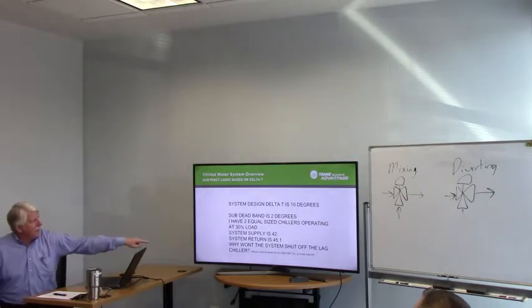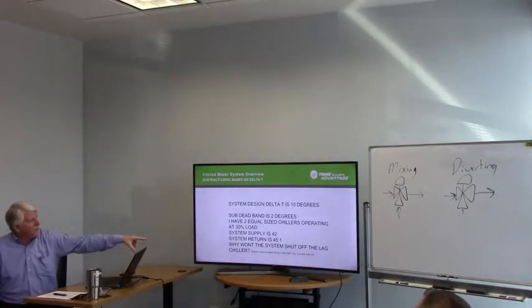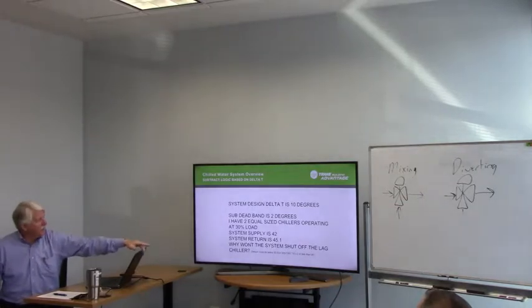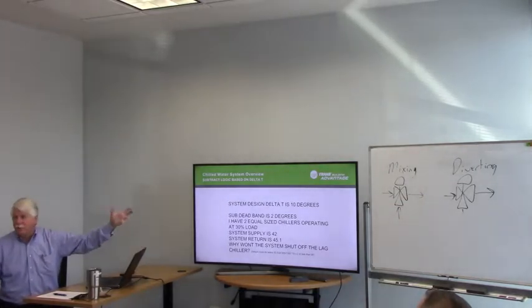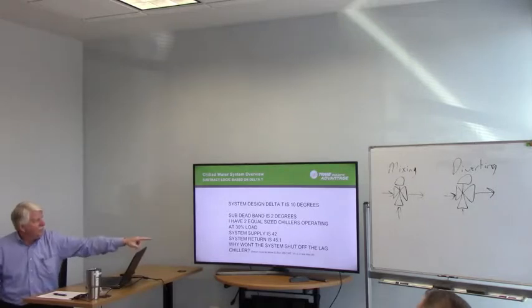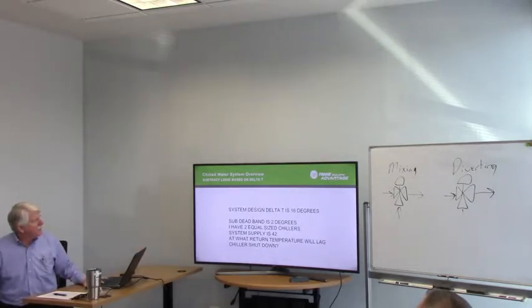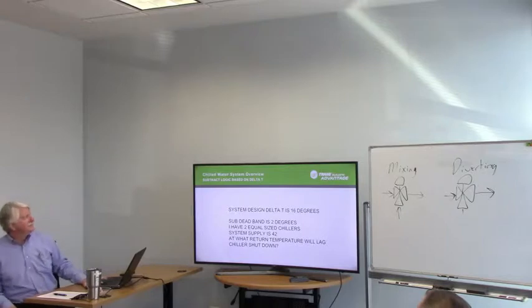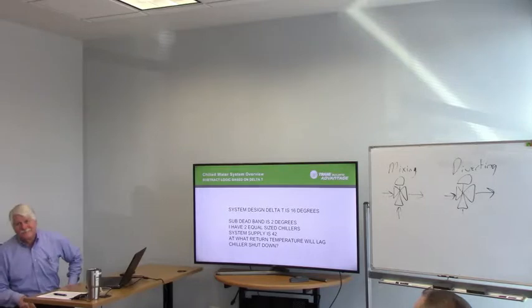See, the return has to be below 52 minus 5, and that fraction of that 5 comes from the percentage of load you want to turn off. I'm saying you want to turn off a 500-ton chiller and you've got 1,000 tons available, minus 2, or less than 45. Okay, this is the hardest question you'll get. Oh, wait a minute, no, I got one harder than this, I'm sorry.